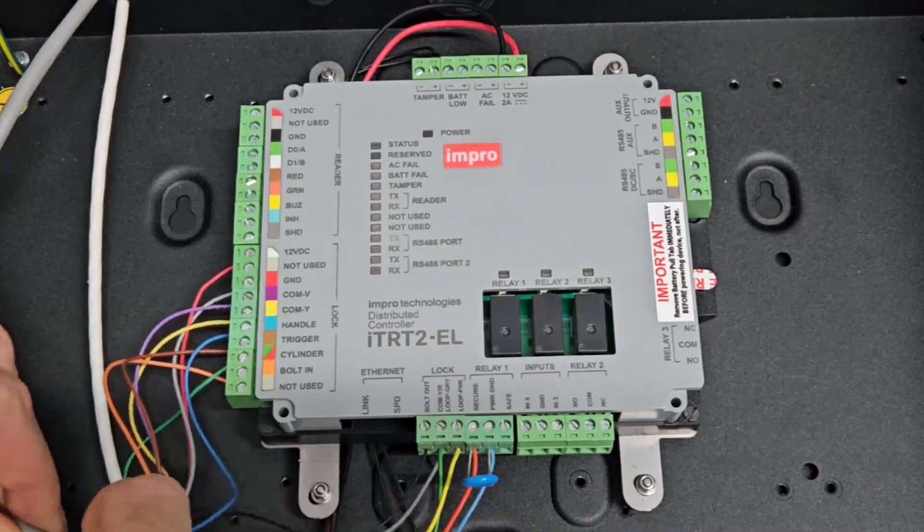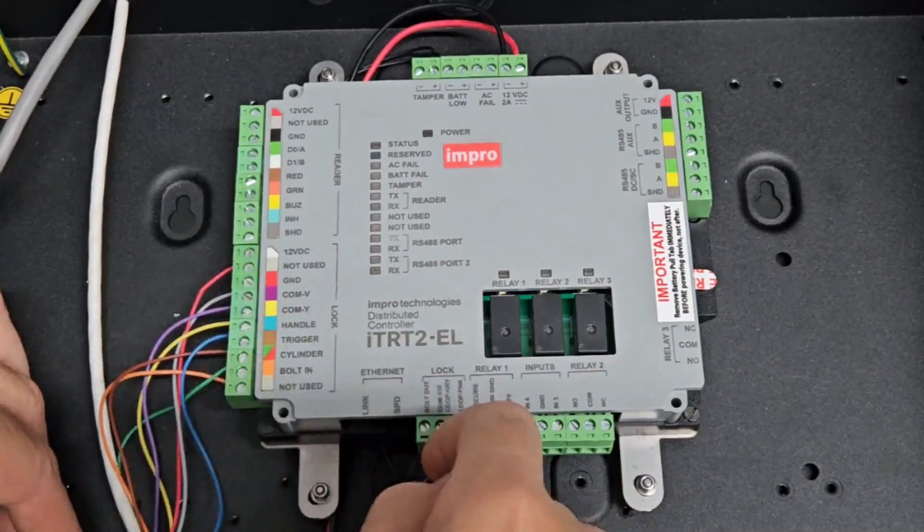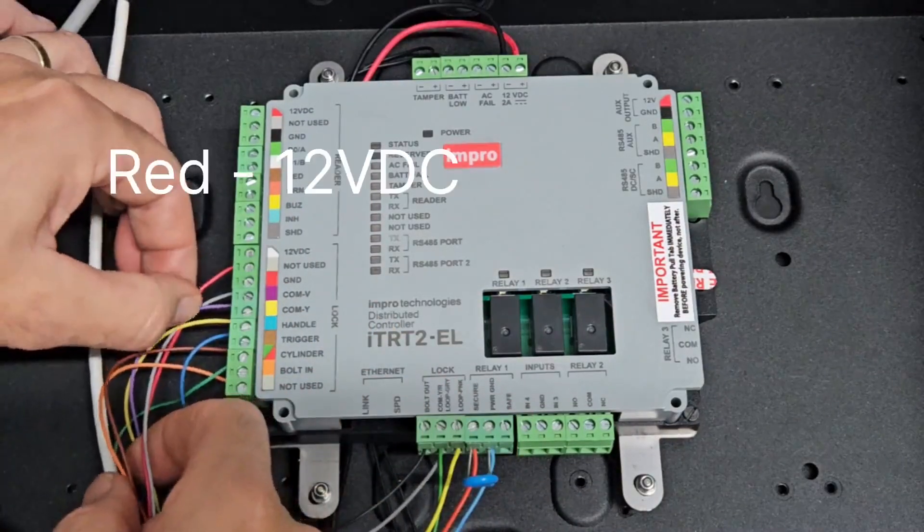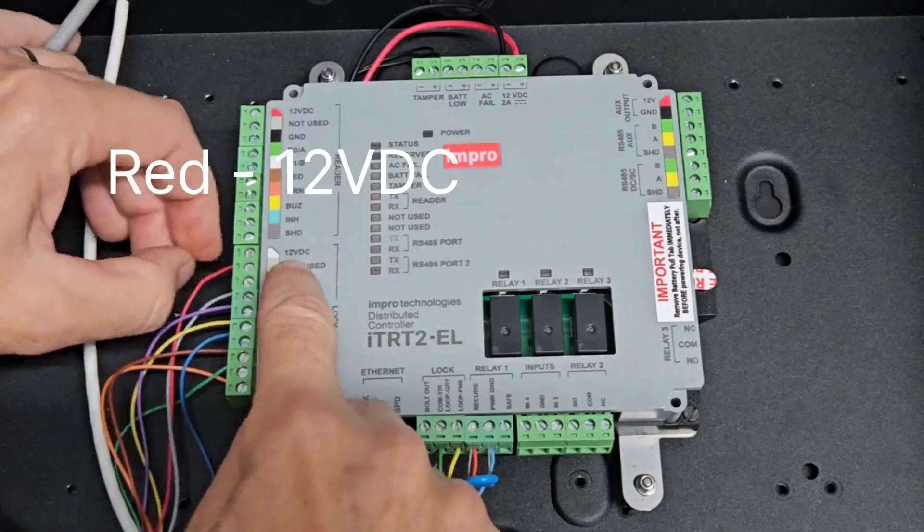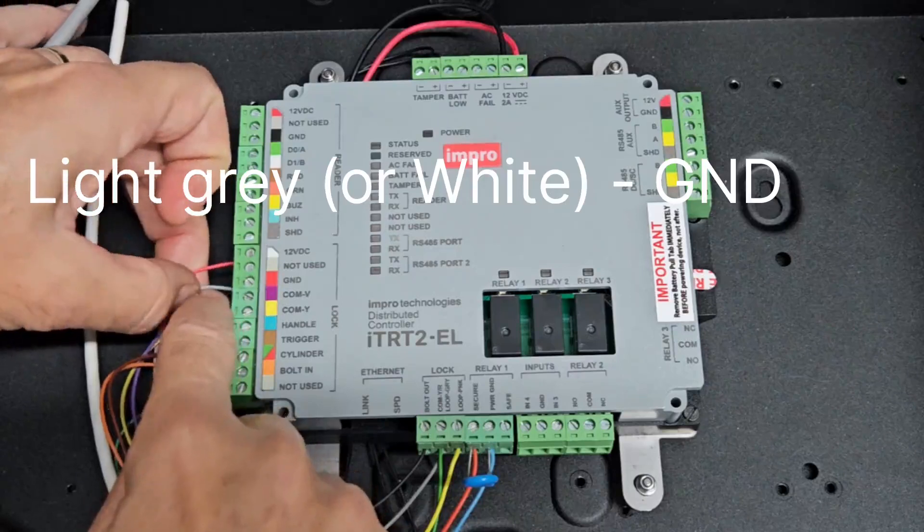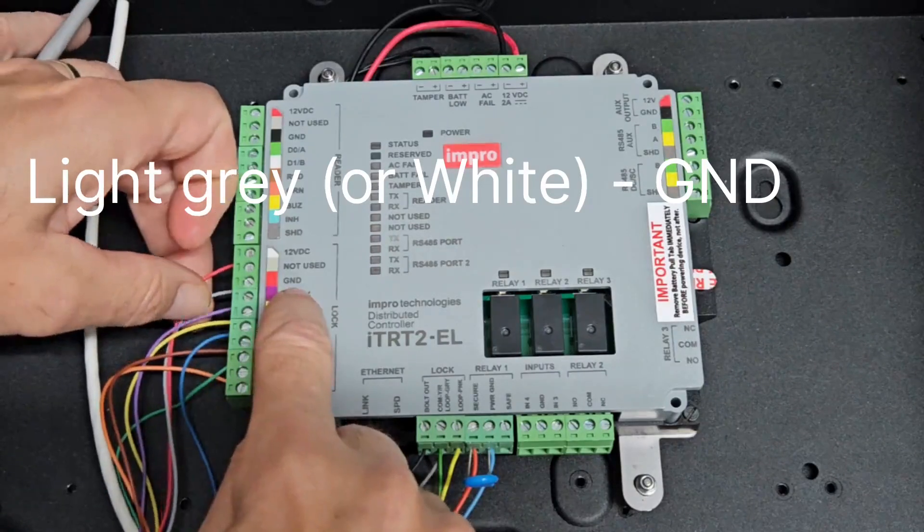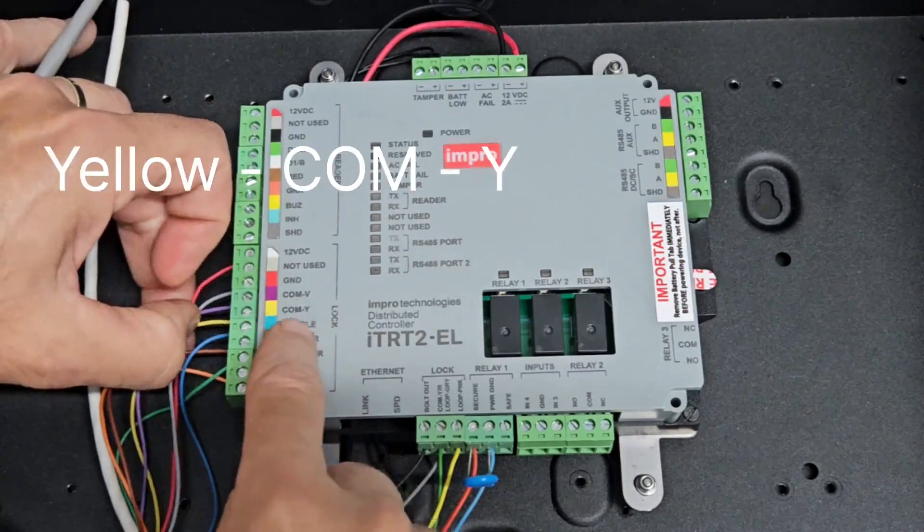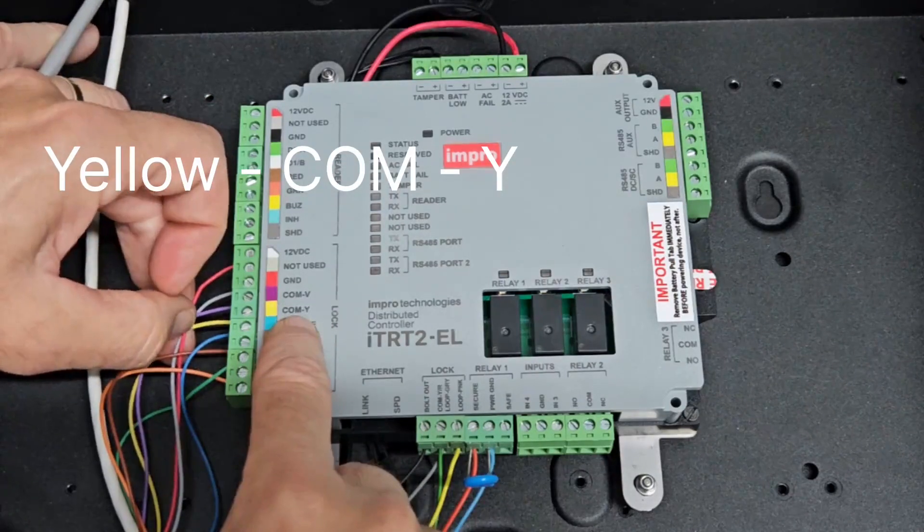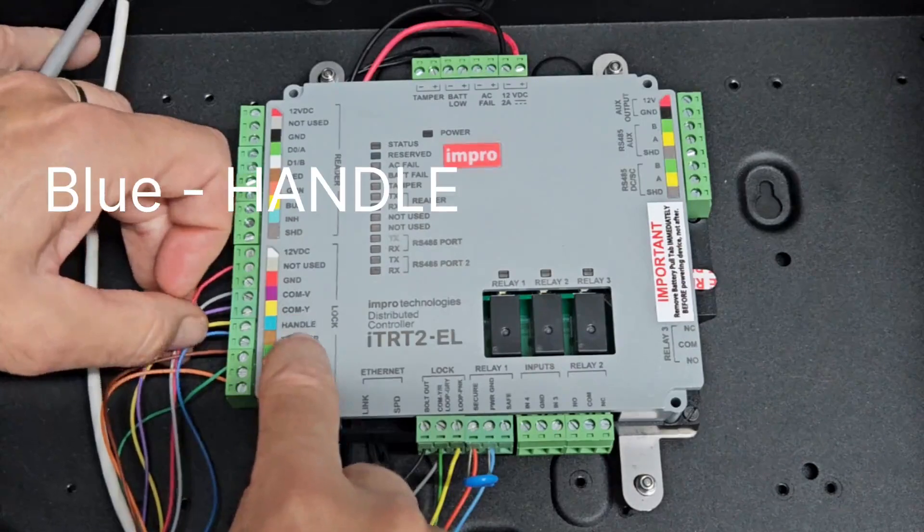Beginning with the 10-core data cable, moving around this corner here. We'll start with a red wire going to 12 volts DC, a light grey or white wire going into ground, a purple wire going into COM V, yellow going into COM Y, blue into handle.